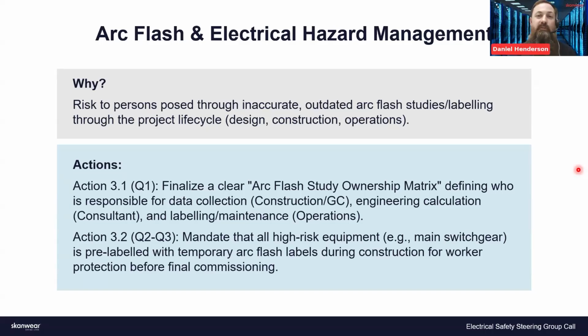Especially in renewables, from my experience being a high voltage senior authorized person in that industry, everything looks the same, especially in wind. You've got big metal, steel towers, all grey, battleship grey. So it's about physically checking your switching program, checking the labels on the gear, because a lot of people I know have gone to the wrong location, purely because signage was incorrect. Maybe signage on the outside of the wind turbine was wrong but the actual signage on the switchgear was correct, and they've gone to the wrong location. It's much easier to make that mistake somewhere everything looks the same, compared to a fixed building where things are in a set location. But it does happen, you've got to make sure you're in the right place, definitely.